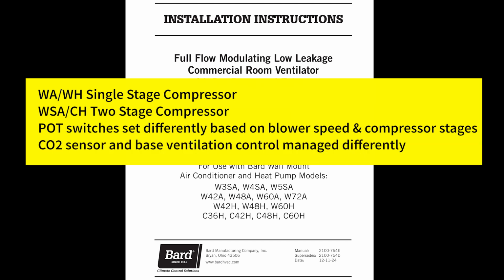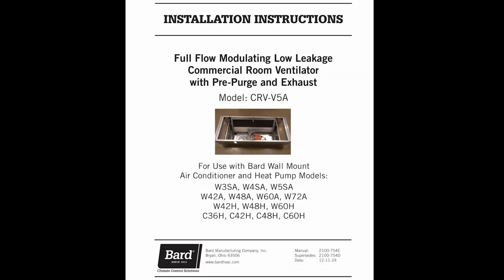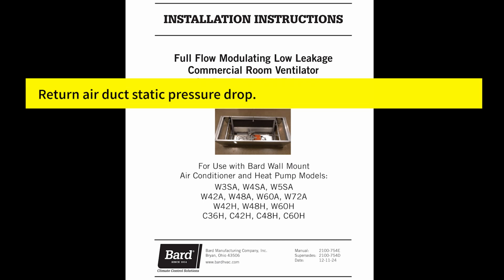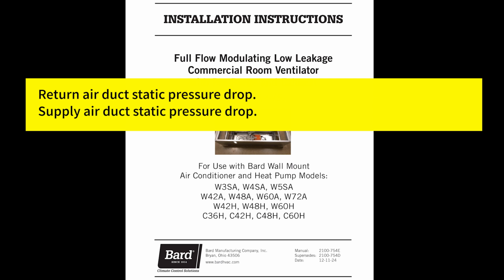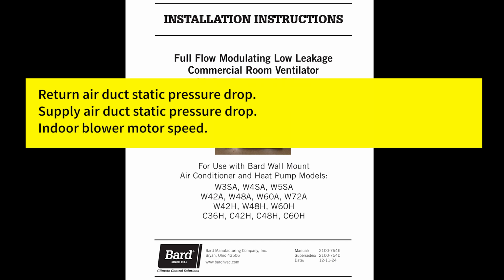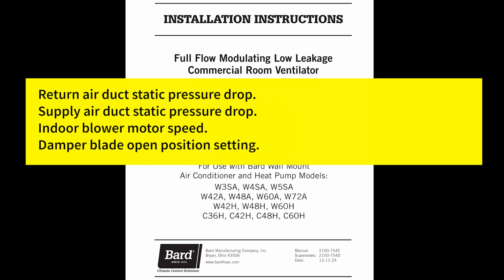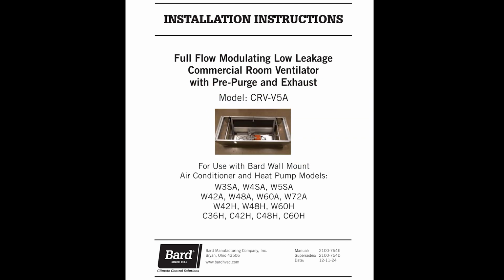Another detail about the control board setting is the difference between a CO2 sensor controlled ventilation process and a basic unit controlled ventilation process. The amount of ventilation air supplied by ventilation devices is dependent on four factors: return air duct static pressure drop, supply air duct static pressure drop, indoor blower motor speed, and damper blade open position setting. Refer to the appropriate CFM graphs of your specific vent device to determine the blade setting necessary to achieve the ventilation air required for each operating mode.